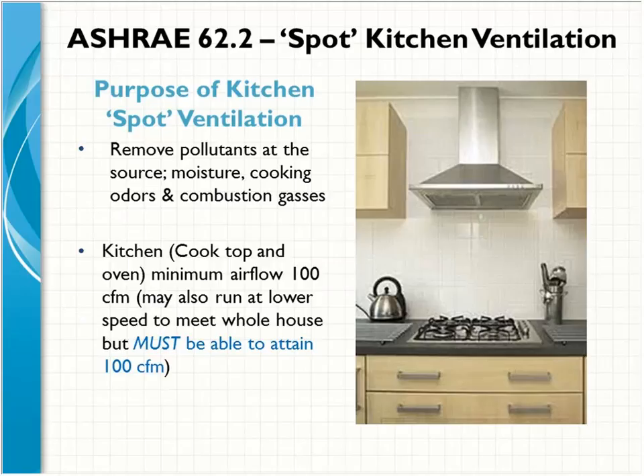Cooktops must be able to do 100 CFM in order to meet the code. I don't know. I haven't seen a HERS rater test a range hood, to be honest with you, so I'm not sure how often that's actually being done. But I do know that in some of the codes, you can use an unvented range hood as long as there's another fan in the kitchen that's capable of running at 100 CFM to meet the requirement for the kitchen as well. So that's another approach, if you don't want to actually vent the range hood.